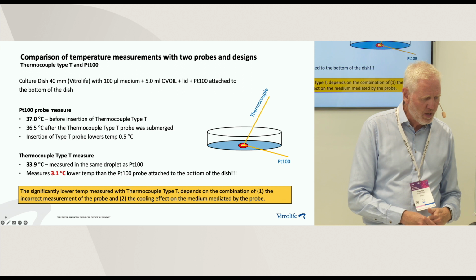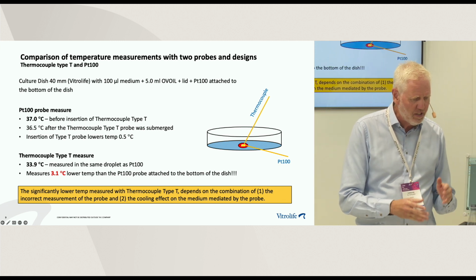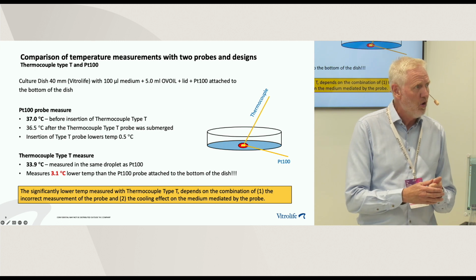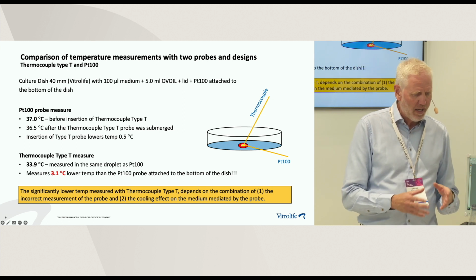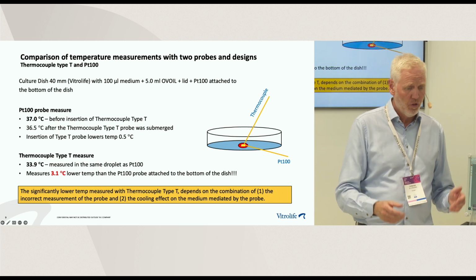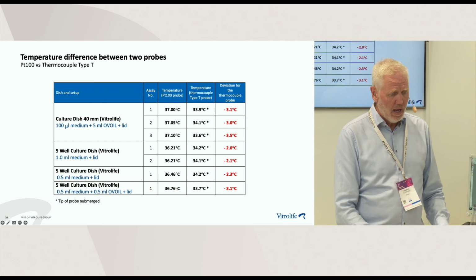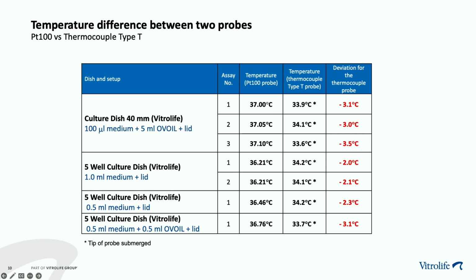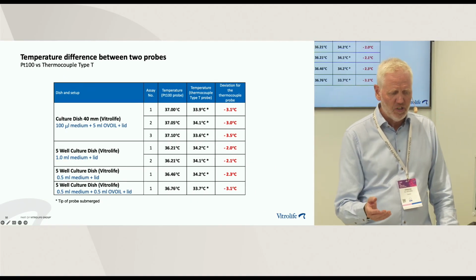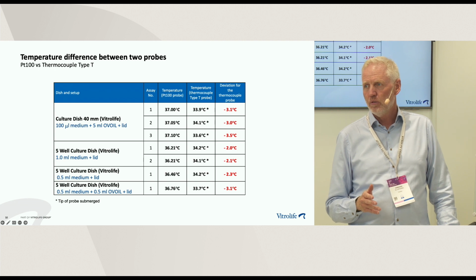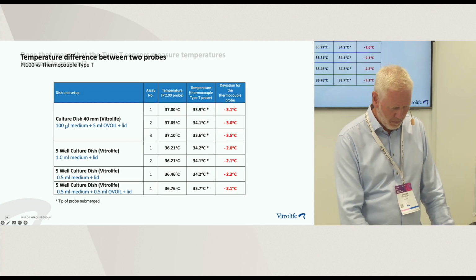So the significantly lower temperature measurement of thermocouple type T depends on the combination of, one, the incorrect measurement of the probe, and two, the cooling effect on the medium mediated by the thermocouple type T. So we did a lot of measurements, and we measured in different dishes, different setups, different volumes. And in the column to the right, the red numbers you see, that's the lower temperature you measure with a thermocouple type T. It's constantly below what you measure with PT100. So the conclusion is that the thermocouple type T probe measures a significantly too low temperature. And we're talking about several degrees here.